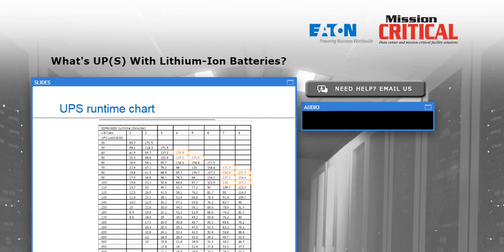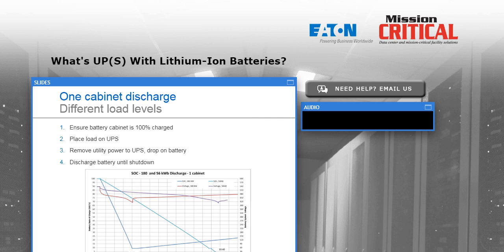So we can configure batteries for that time if you'd like, but it tends to be sometimes less expensive to look at an 8-minute battery rather than a 5-minute battery, just based on the amount of cabinets that would be needed. So consult with your UPS vendor or your battery vendor to make sure you have a proper sized battery.